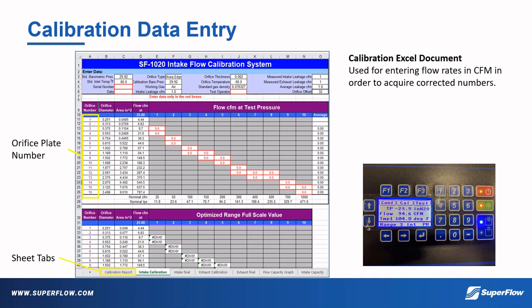These orifice numbers along the left correspond to the calibration plates, while the numbers shown along the top correspond to the flow ranges of the bench. The flow rates found while flowing the bench with an orifice plate in a specified range are recorded along this diagonal in its respective box.